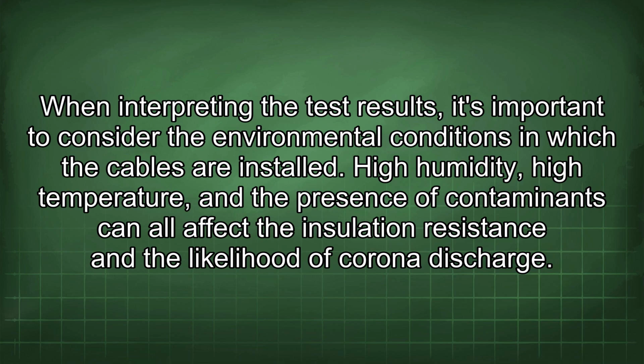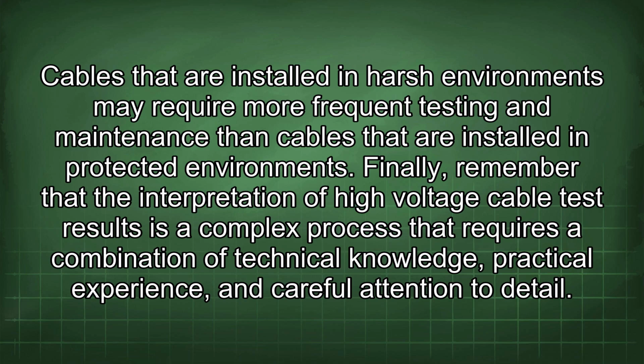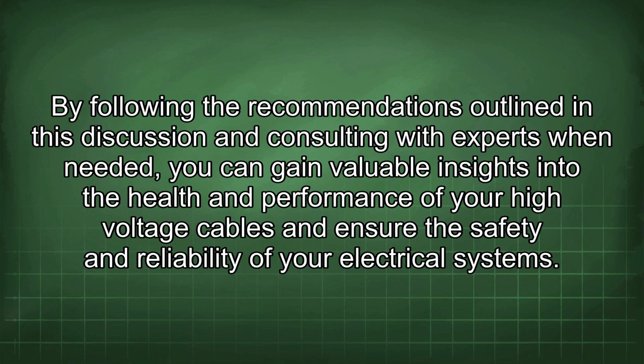When interpreting the test results, it's important to consider the environmental conditions in which the cables are installed. High humidity, high temperature, and the presence of contaminants can all affect the insulation resistance and the likelihood of corona discharge. Cables that are installed in harsh environments may require more frequent testing and maintenance than cables that are installed in protected environments. Finally, remember that the interpretation of high-voltage cable test results is a complex process that requires a combination of technical knowledge, practical experience, and careful attention to detail. By following the recommendations outlined in this discussion and consulting with experts when needed, you can gain valuable insights into the health and performance of your high-voltage cables and ensure the safety and reliability of your electrical systems.